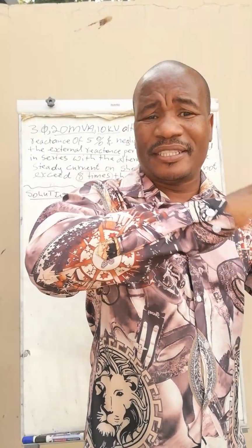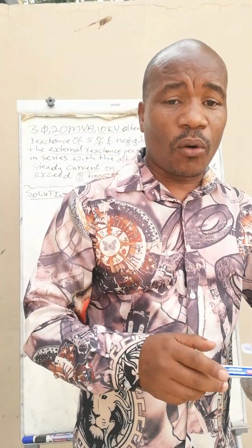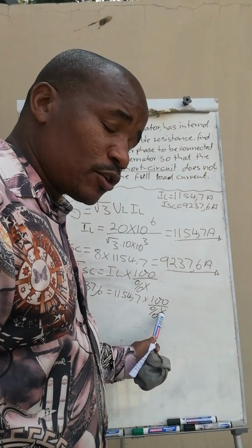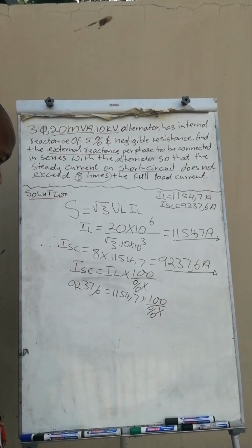They allow the engineer in the field to do rapid fault calculations easily. Using the transformation ratio is difficult because the system becomes unstable; you have to multiply or divide by the square of K and so on. That makes the situation very difficult. So in practice they prefer per unit or percentage reactance.